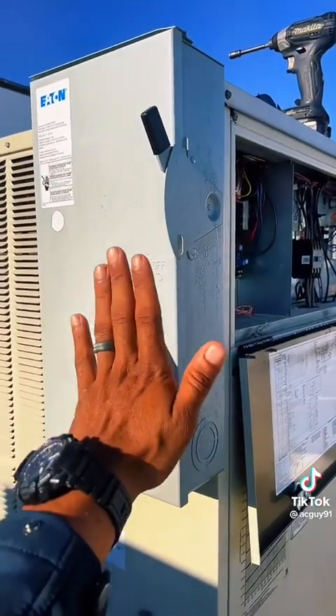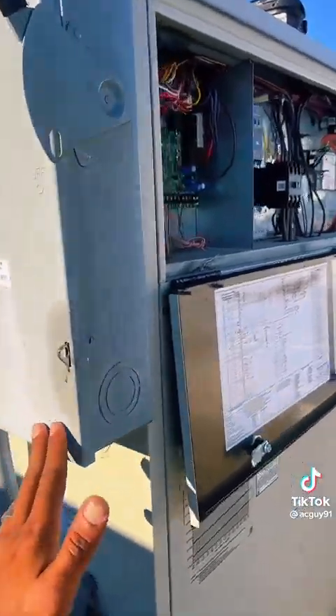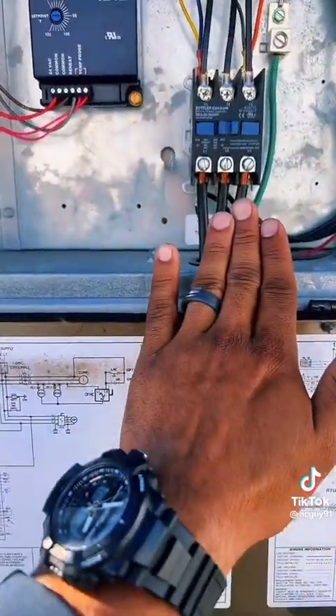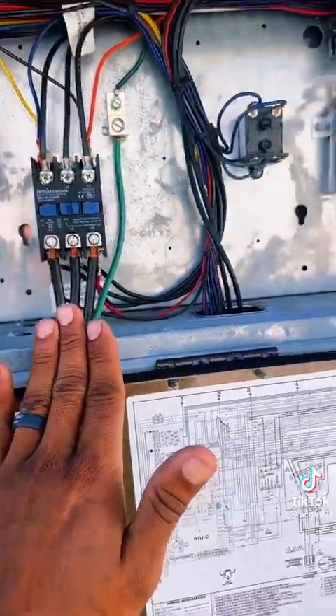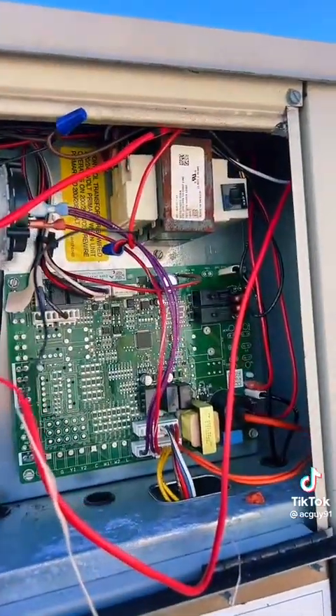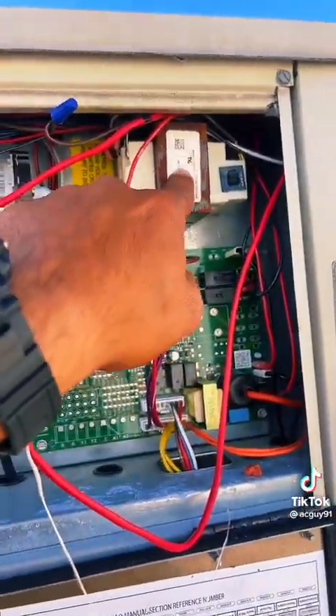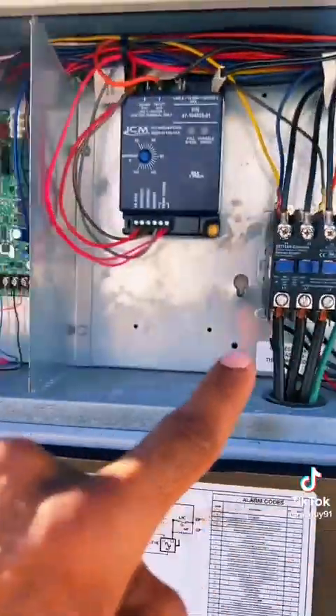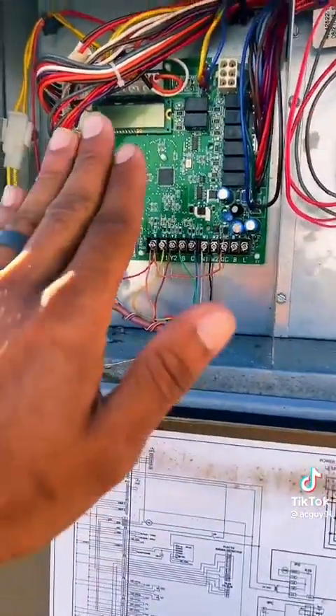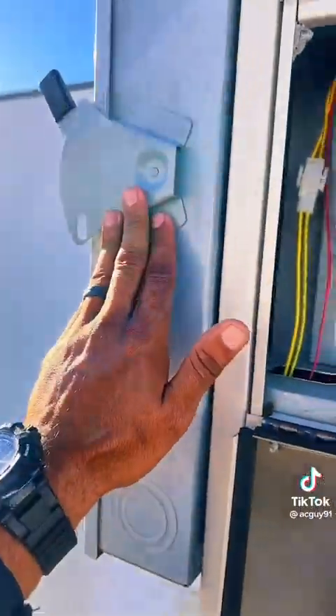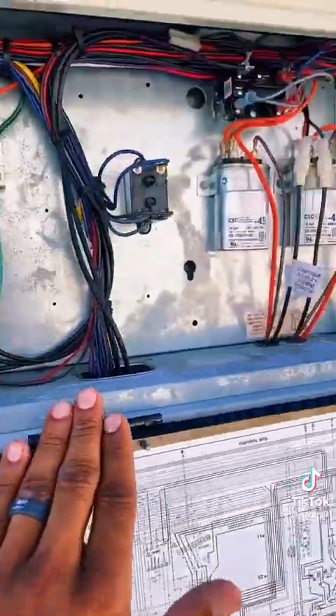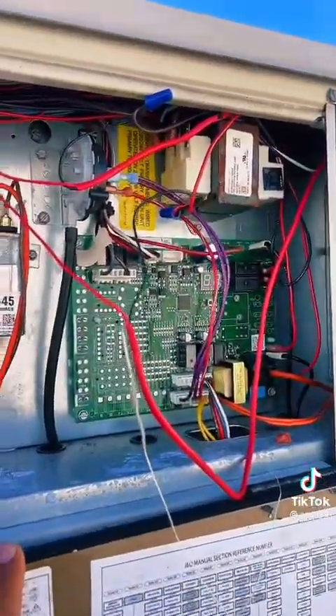Remember, we started at the disconnect. We had power coming in. We have power coming out. From here, this line voltage is gonna go over to my transformer. That's gonna transform my high voltage to low voltage and send power back to this. We've already verified we have no power here. I do have power here. I do have power here. What's that mean, guys? It's time to go to that transformer.